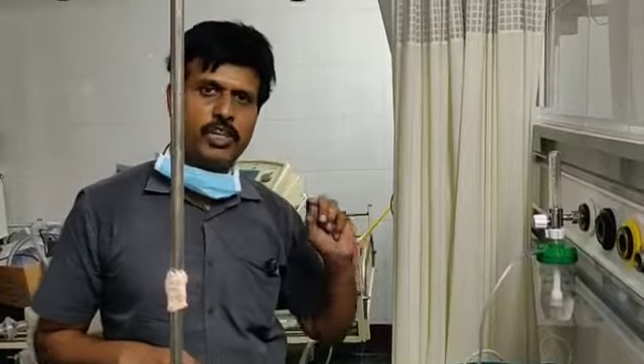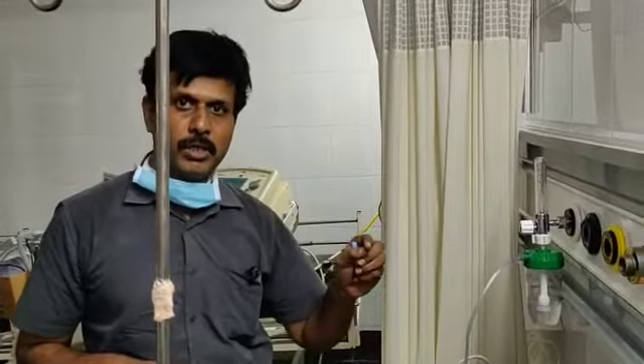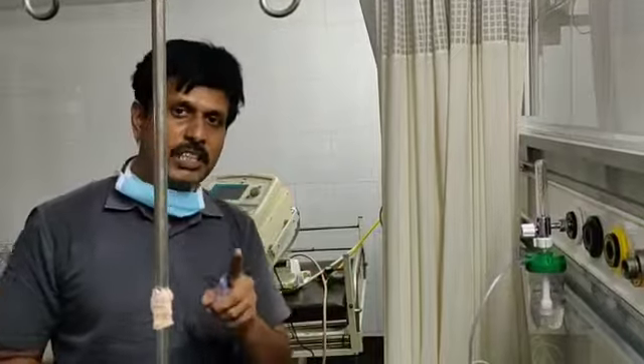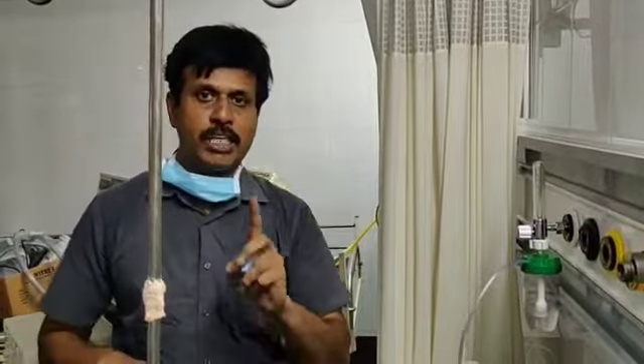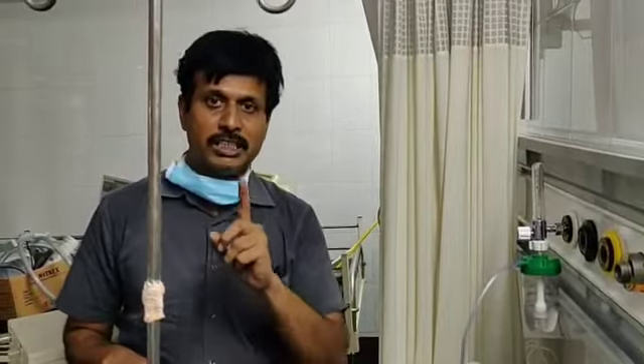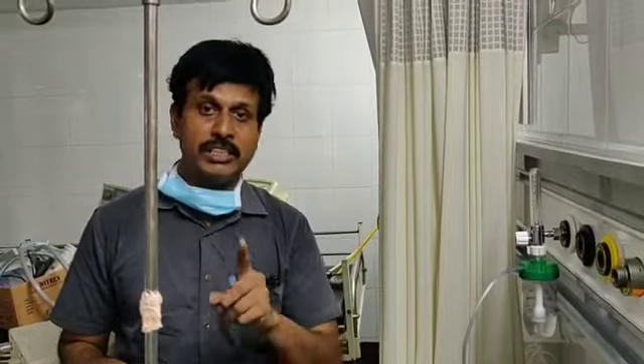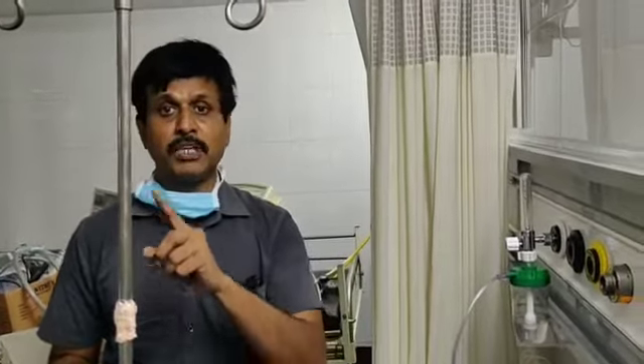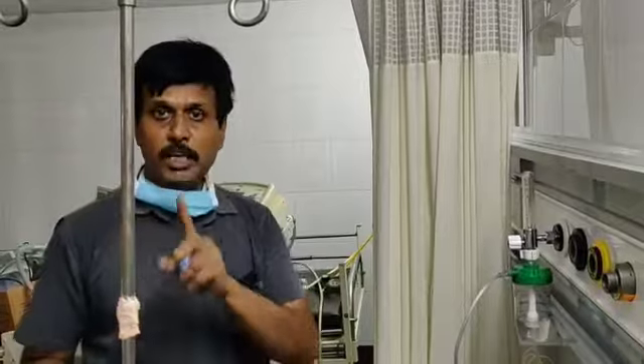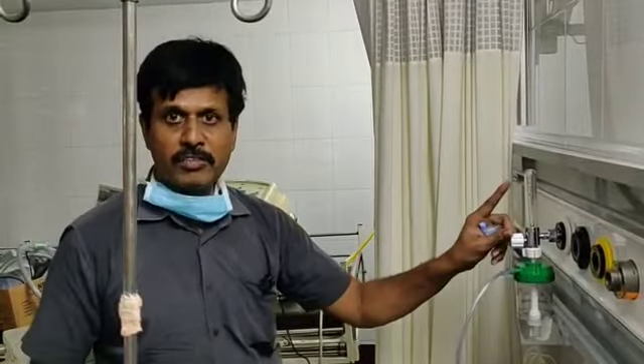Now you can see how we are making CPAP without a ventilator. This will replace the HFNC, high flow nasal cannula ventilation. Using high flow nasal cannula, you need 60 to 70 or 80 liters per minute of oxygen, which has to be wasted. Here I am going to waste only 10 to 15 liters of oxygen.